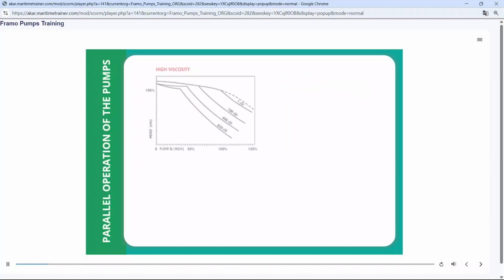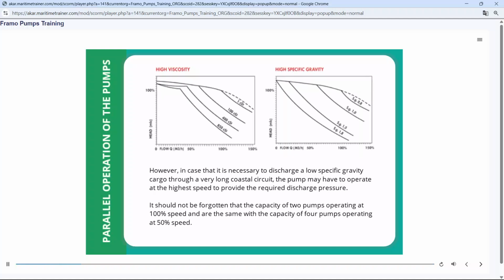However, in case it is necessary to discharge a low specific gravity cargo through a very long coastal circuit, the pump may have to operate at the highest speed to provide the required discharge pressure. It should not be forgotten that the capacity of two pumps operating at 100% speed is the same as the capacity of four pumps operating at 50% speed.